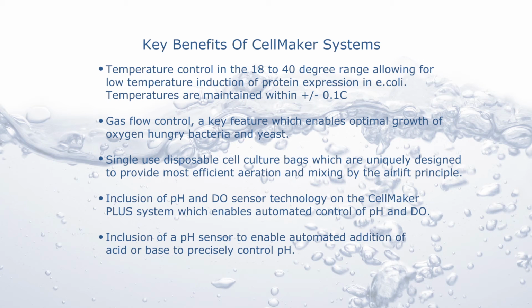Single-use disposable cell culture bags which are uniquely designed to provide the most efficient aeration and mixing by the airlift principle. Inclusion of pH and DO sensor technology on the Cellmaker Plus system, which enables automated control of pH and dissolved oxygen. Inclusion of a pH sensor to enable addition of acid or base to precisely control pH.